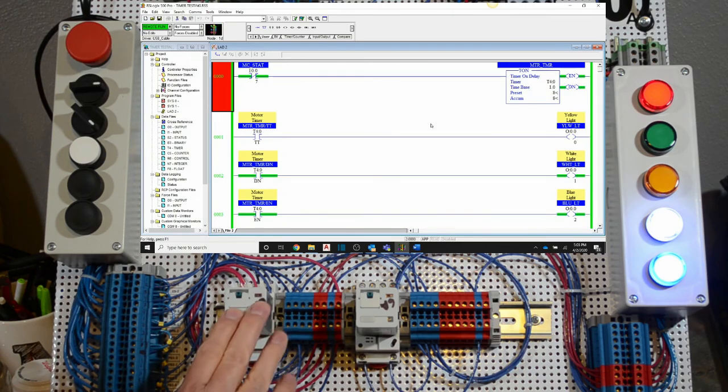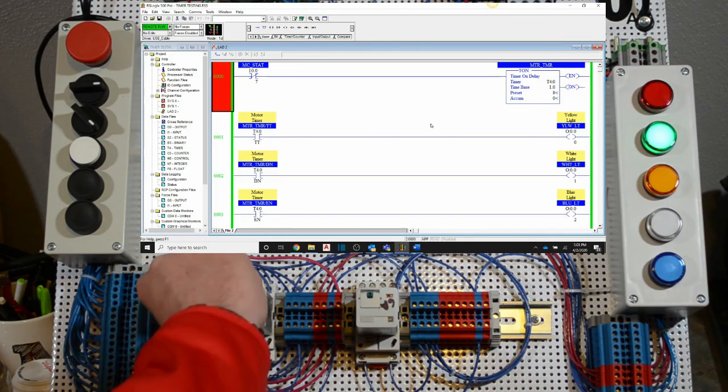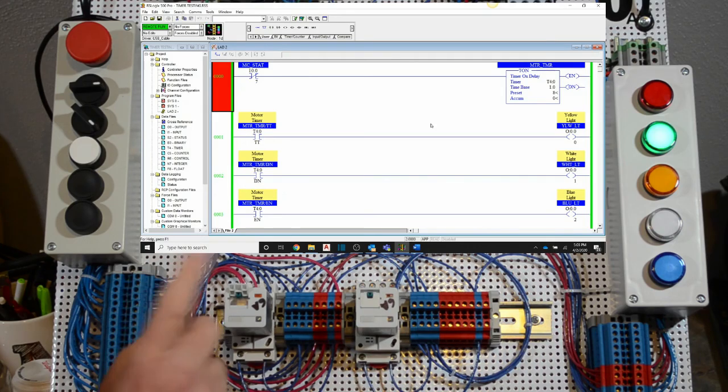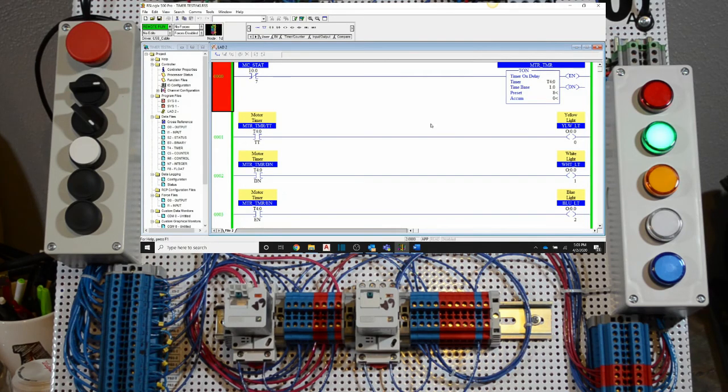So we don't have a program that I can actually start and stop the motor, but I can manipulate it right here on the relay. We have this little gate that I can manually open up, and that simulates some external device starting the motor. So now with the motor started, of course we have the green light because that's wired external to the PLC, and that's saying that we have 120 volts going to our theoretic motor. We don't actually have a motor wired to our control relay. And as long as the motor is running, we don't have any of our bits set on our timer.